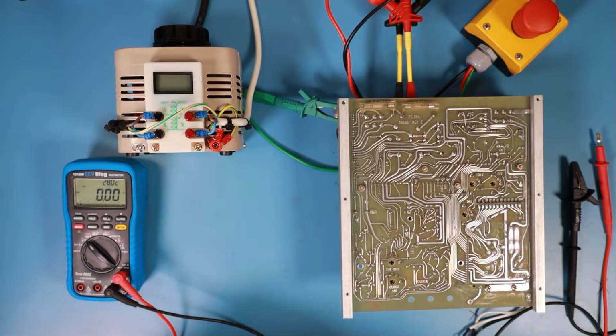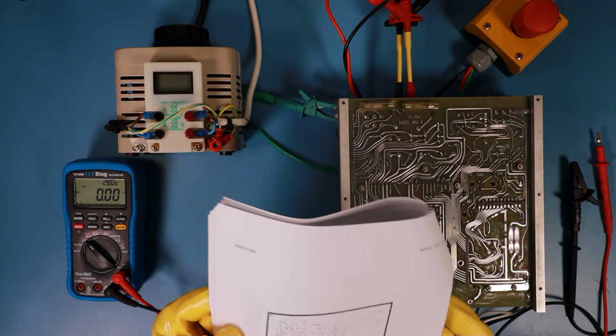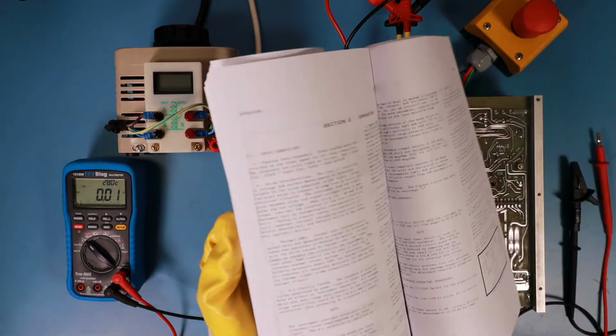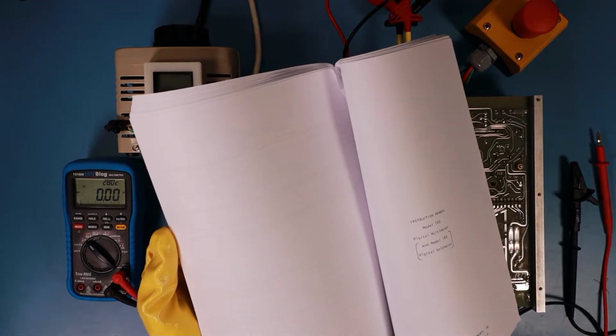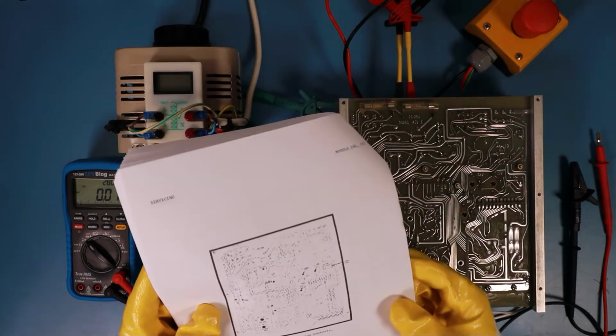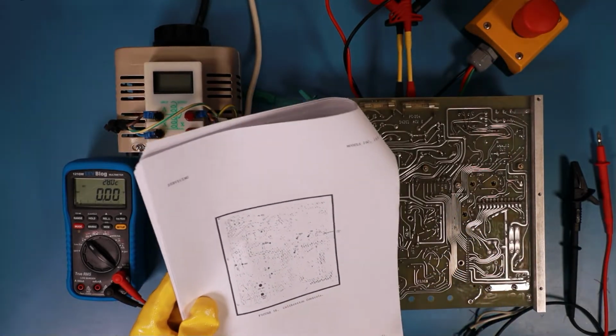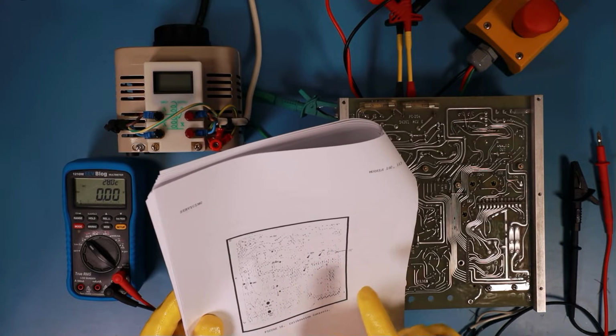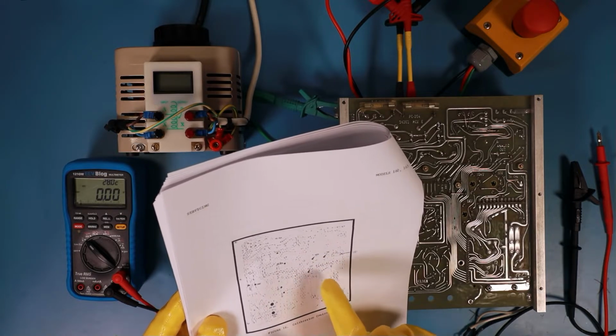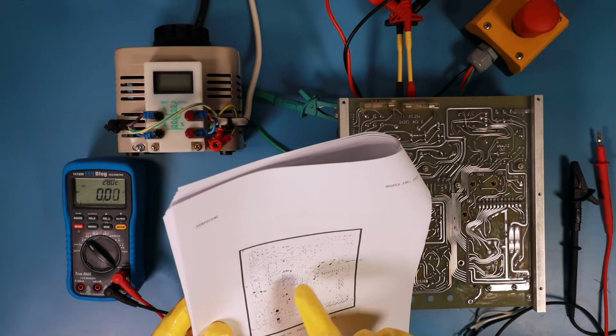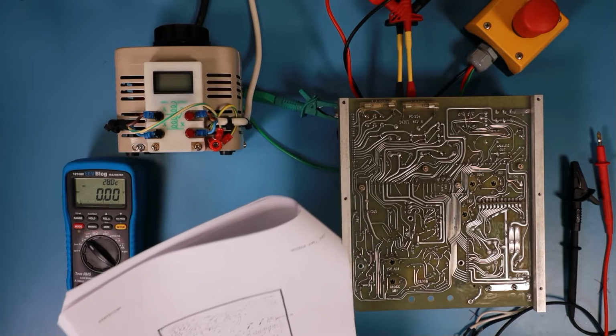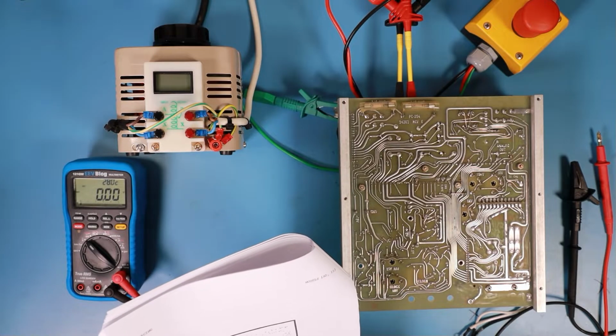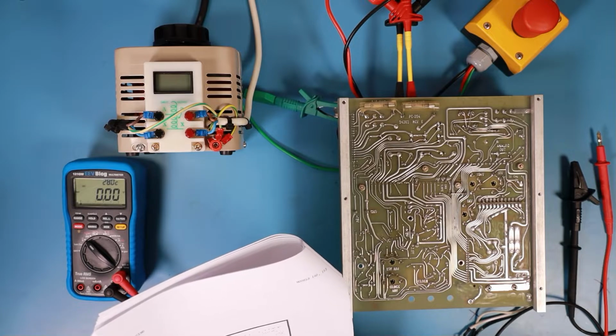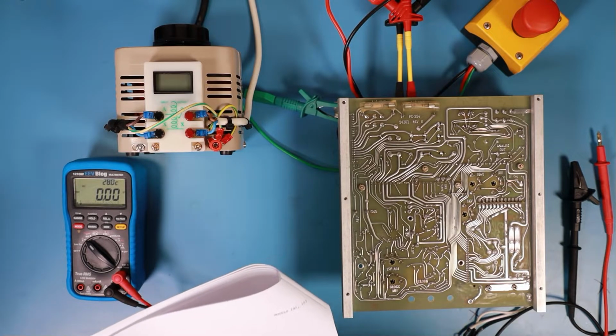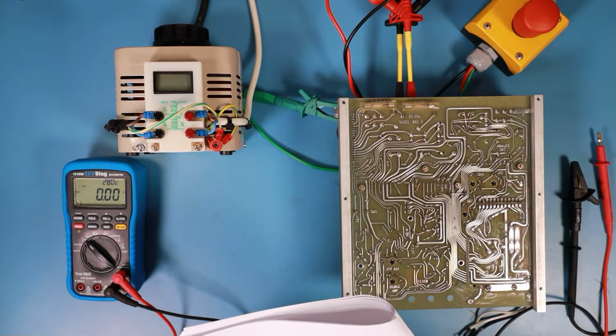So just in case you're wondering what I'm doing and how I am able to do this, I found the schematics and manual of this instrument online. It's easy to find, just Google it. And there's a page which describes where the voltage points are. So not only the voltage points for calibration, also the voltage points for the internal voltages. And I'll just slowly ramp up the voltage and check that the voltage lines don't go too high. And I hope it won't burn up on me.